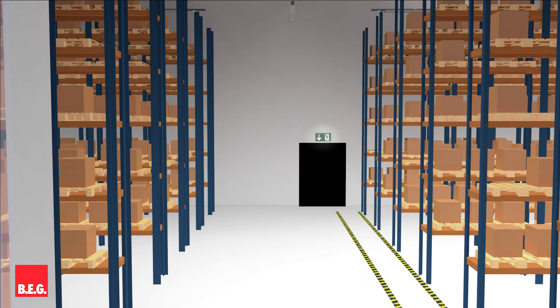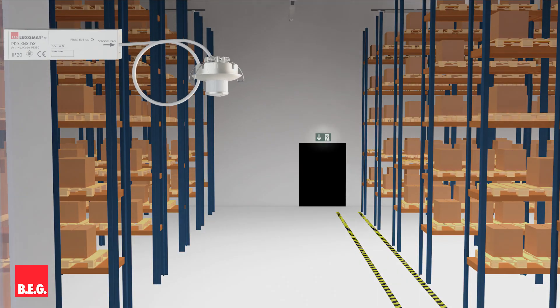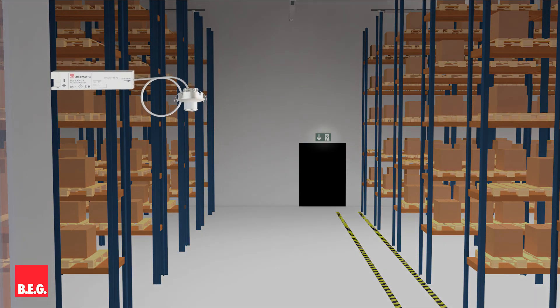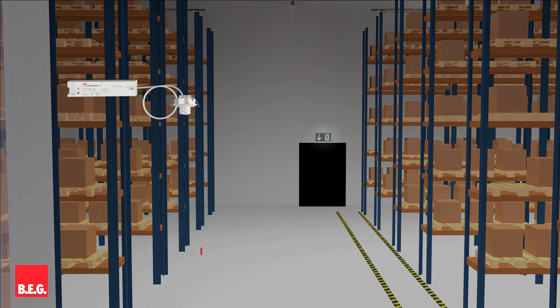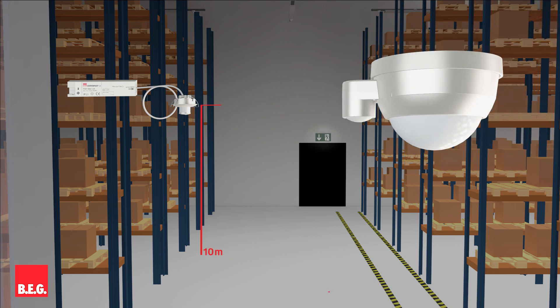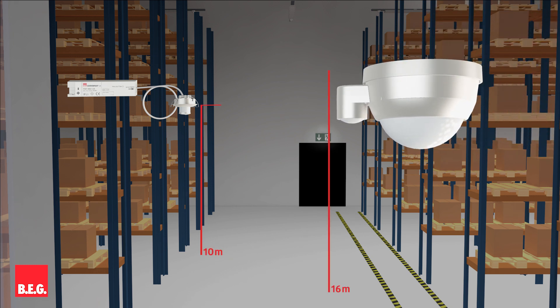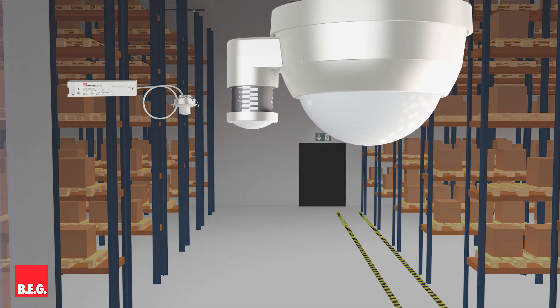For large mounting heights, such as in warehouses, we have the PD9 for a mounting height of up to 10 meters and the PD4 for a mounting height of up to 16 meters. These have a telescope-like sensor which can measure the brightness reliably at these greater heights.